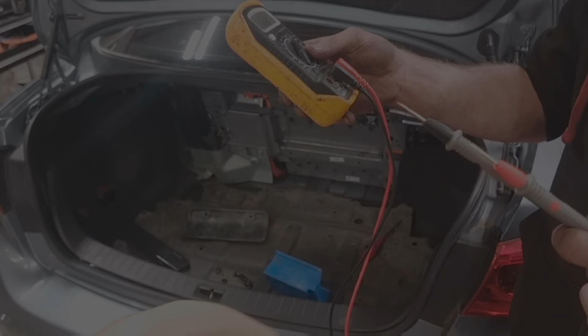Right, so do you want to just explain what you're doing? You just want to see that there is under 1 ohm of resistance, it says. We'll set the meter to ohms, and we'll set it to the lowest ohms possible, which is over there, 200. And then just literally, if we touch these two leads together, if you come down with that a little bit, when we touch these leads together, it should be perfectly zero. There is a little bit of resistance somewhere, but it's good enough for this test.